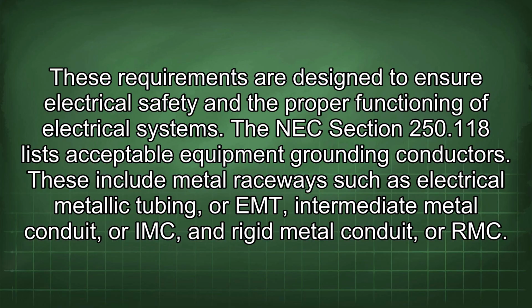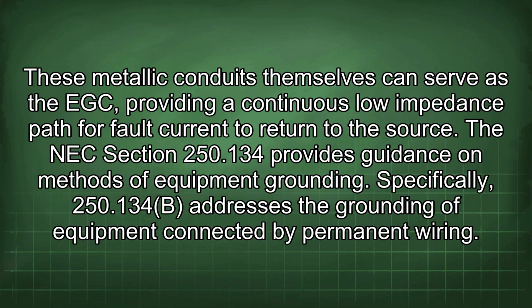The NEC Section 250.118 lists acceptable equipment grounding conductors. These include metal raceways such as electrical metallic tubing, or EMT, intermediate metal conduit, or IMC, and rigid metal conduit, or RMC. These metallic conduits themselves can serve as the EGC, providing a continuous low impedance path for fault current to return to the source.